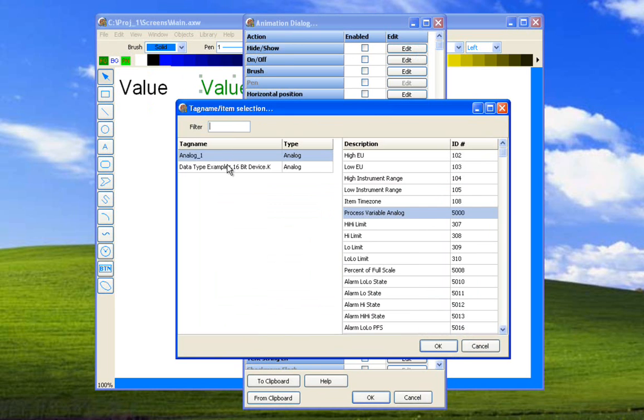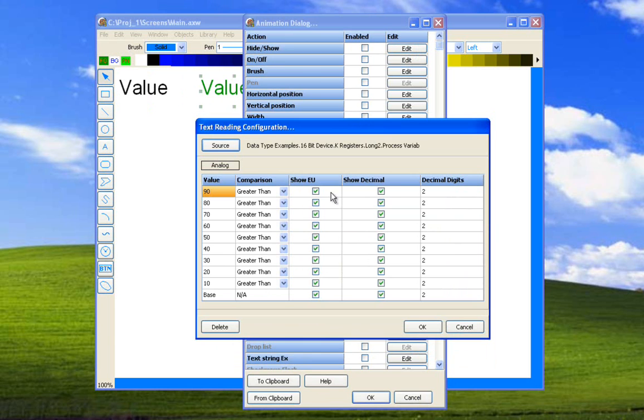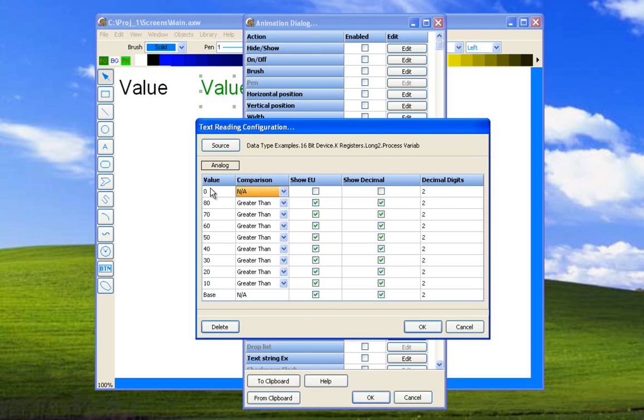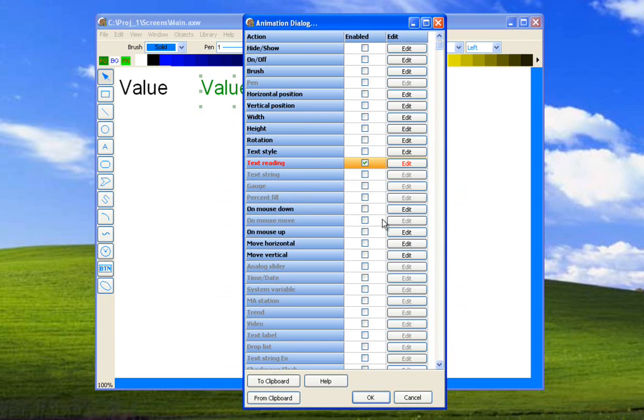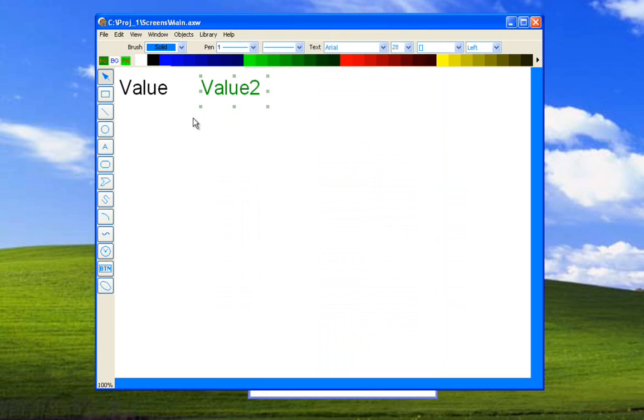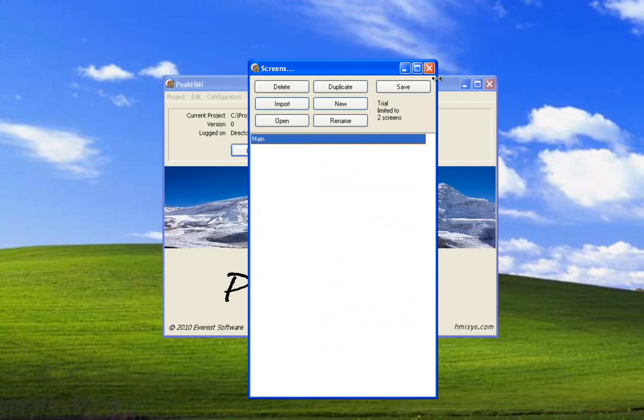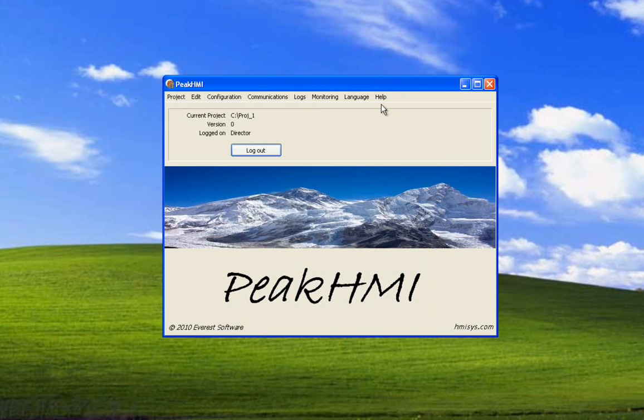We're going to select source. Here's our tag name, process variable analog. We're going to not use any of these settings over here. So we just say NA for comparison, which means when it's scanning, it starts at the top and scans to the bottom. If it gets to here, it uses these. Otherwise, it looks for a comparison to match and then it uses these settings. Since we set NA as the first one, it's going to use these settings and stop processing. It's faster to do it here than to do it further down. Select OK. Make sure the check box is enabled. Select OK. Select Save. Close and close.